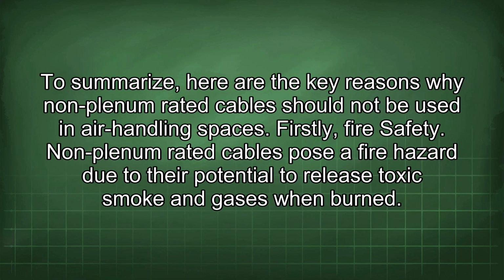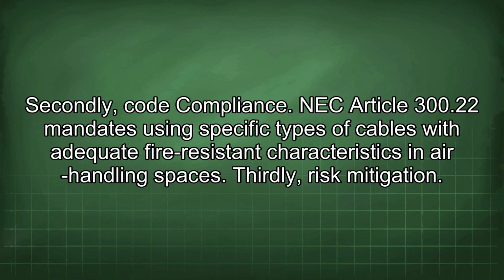To summarize, here are the key reasons why non-plenum rated cable should not be used in air handling spaces. Firstly, fire safety. Non-plenum rated cables pose a fire hazard due to their potential to release toxic smoke and gases when burned. Secondly, code compliance.